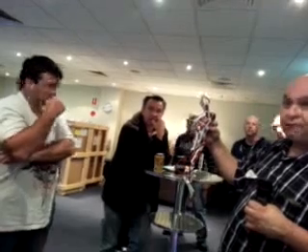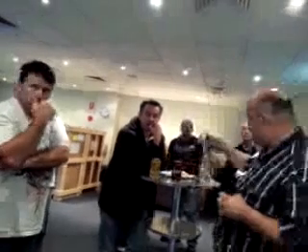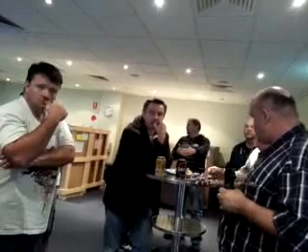Because I'm running 120 of those, and there's one power injection point halfway along. But the power runs along the bottom of every item, so it's only the cable from here to the corner long. Each item comes off that cable. Up here there's a voltage drop, but it's 12 volts, and the cable you're using is a pretty chunky cable, because it's going to take the current of all that load. That's correct.